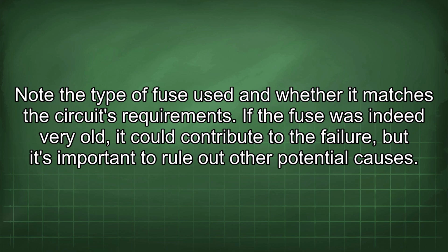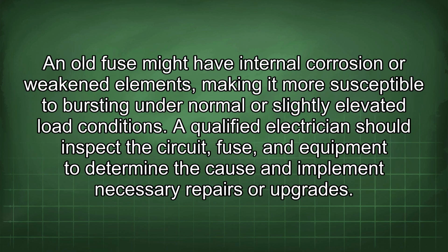If the fuse was indeed very old, it could contribute to the failure, but it's important to rule out other potential causes. An old fuse might have internal corrosion or weakened elements, making it more susceptible to bursting under normal or slightly elevated load conditions.